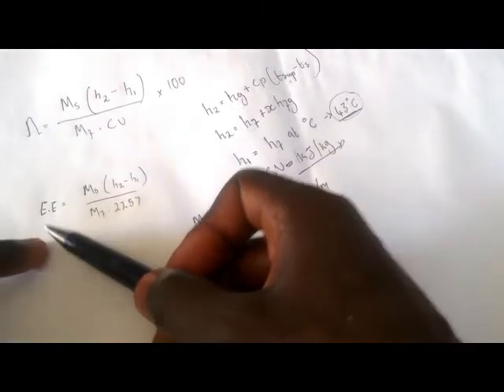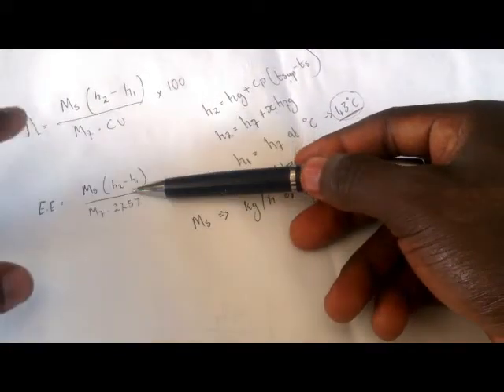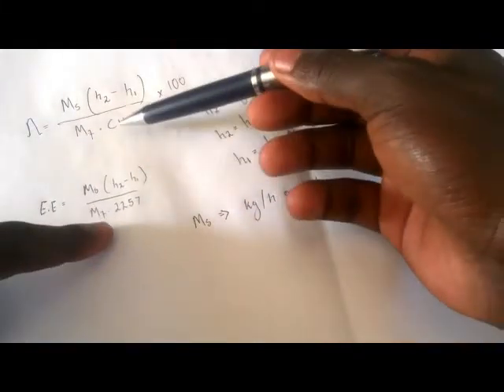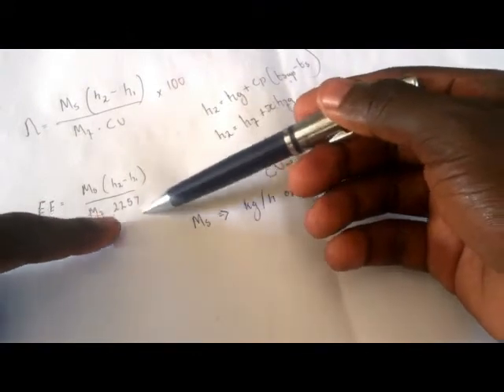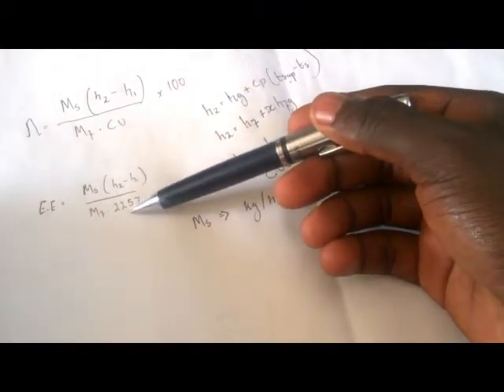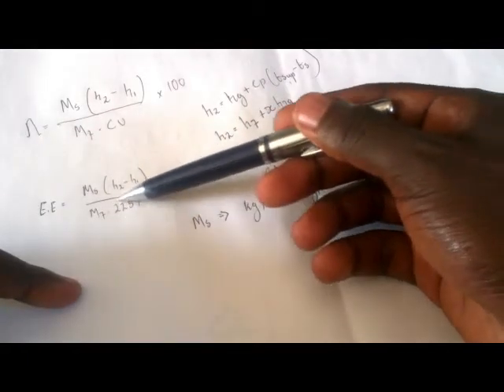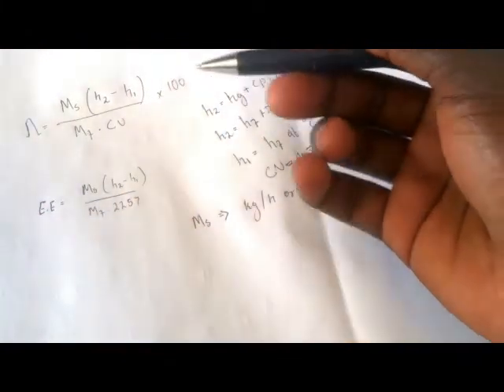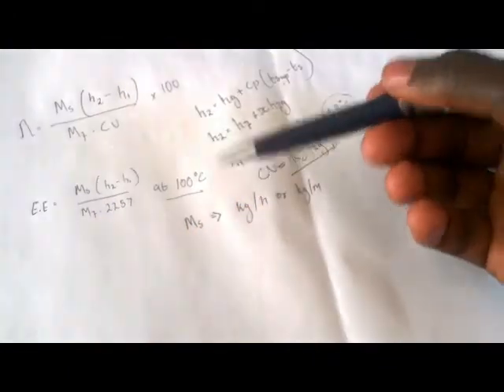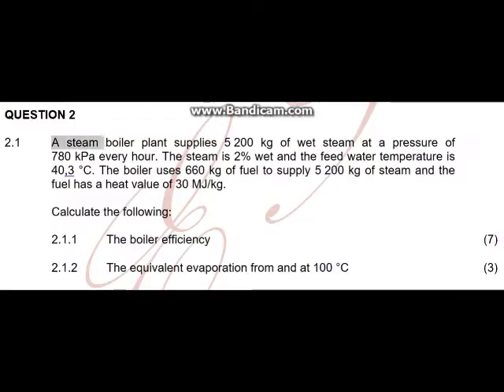When you calculate the equivalent evaporation, it uses the very same formula — the only difference is that instead of the calorific heat value, you use the constant 2257. This 2257 is always constant when calculating equivalent evaporation. Also, the equivalent evaporation is always referenced at 100 degrees Celsius.